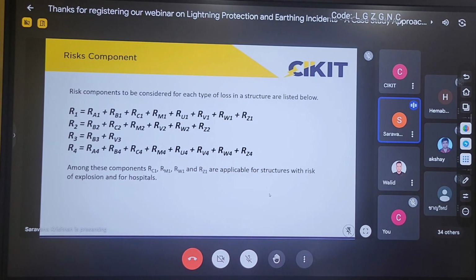And RC is the component related to the failure of electronic equipment inside the structure. If lightning strikes my building, obviously the electronic equipment inside the building may also get damaged, and that is covered by the component RC. From this we can observe that if lightning strikes any structure, it will result in all three damages: injury to human beings, damage to the structure, and failure of electronic equipment. So the first three components are related to lightning directly striking a building. And the fourth one, RM, is the component related to lightning striking near the building.